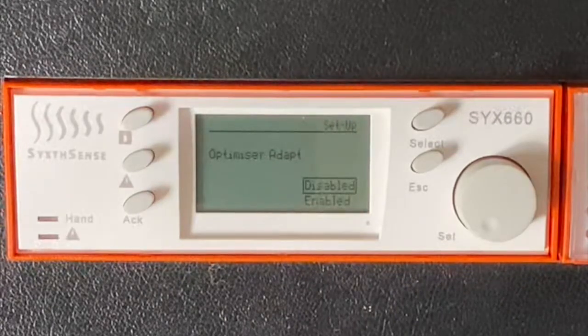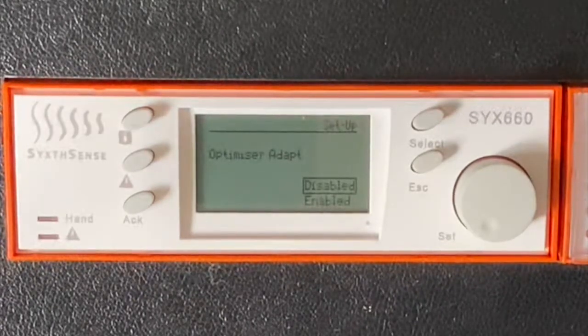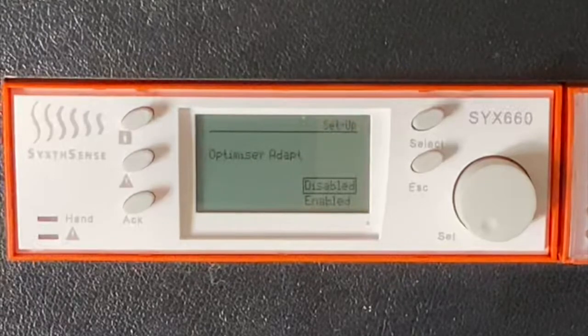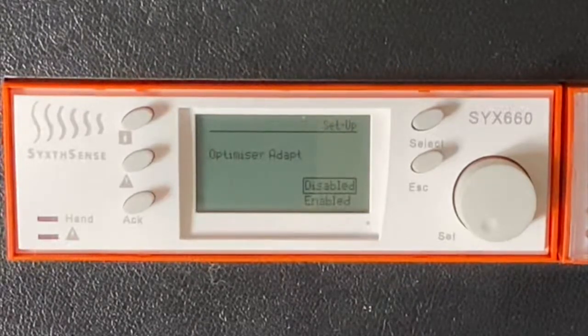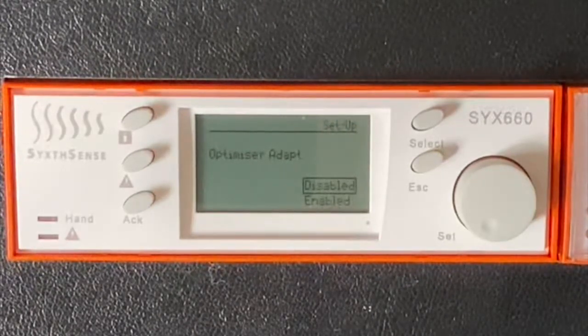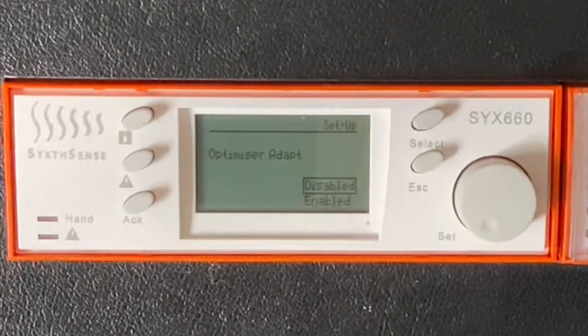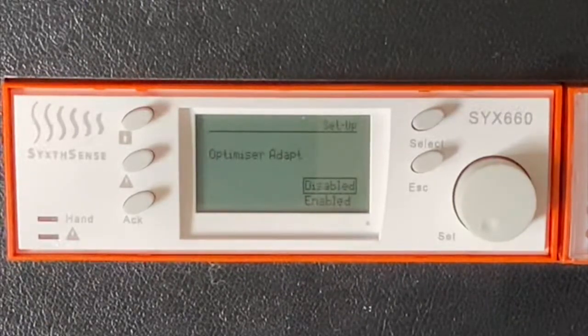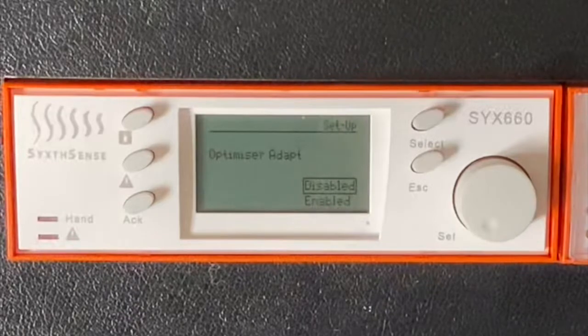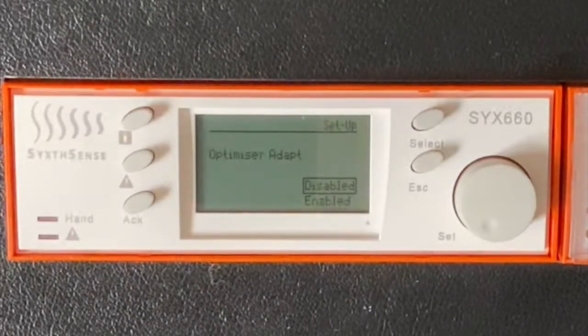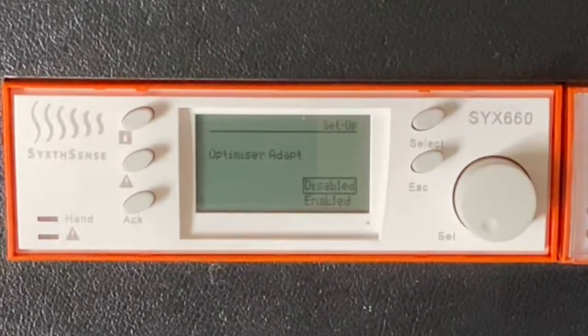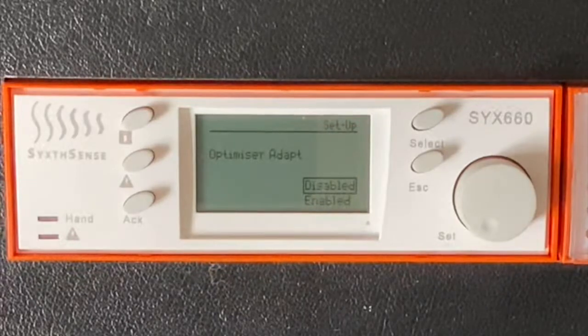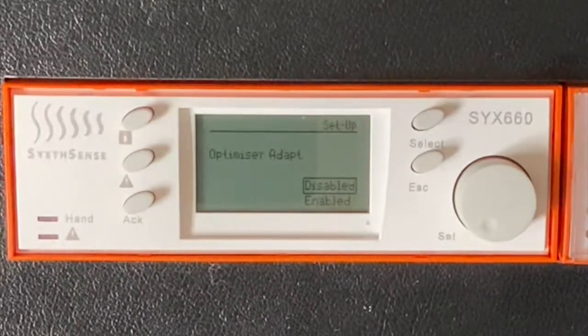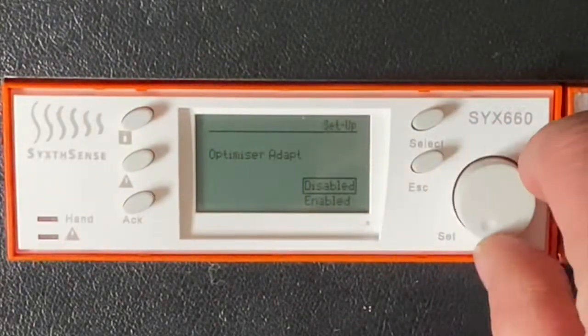So sensor placement and also set points that we try to achieve with the plant will affect the building warm-up rate. Where there are situations that the set point is not achievable for technical reasons or through design reasons, then it may be a factor where we have to disable the adaptation, and this is the parameter that we would set to disabled should we need to do that, but we'll leave ours enabled.